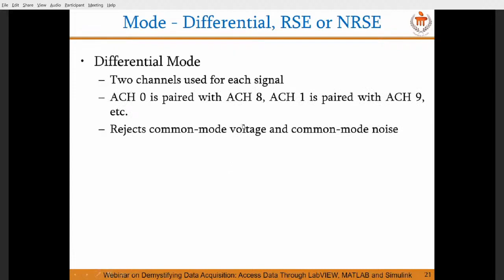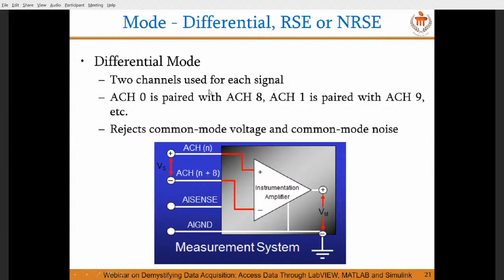So now there is something called differential mode. Usually there will be an instrumentation amplifier. The differential mode is used if your voltage signal is bipolar. If you have a value ranging from minus 10 to plus 10, you obviously have to go with the differential mode of operation, where you connect your signal to two terminals.